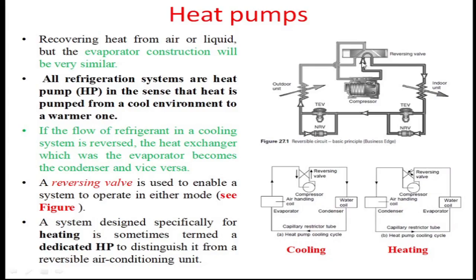When the reversing valve is in the shown direction, the compressor is discharging high temperature, high pressure refrigerant to the indoor unit, rejecting heat to the indoor unit. In this case it is acting as a heat pump — heating the conditioned space. Then the refrigerant goes through the NRV and via the thermostatic expansion valve (TEV) to the outdoor unit.